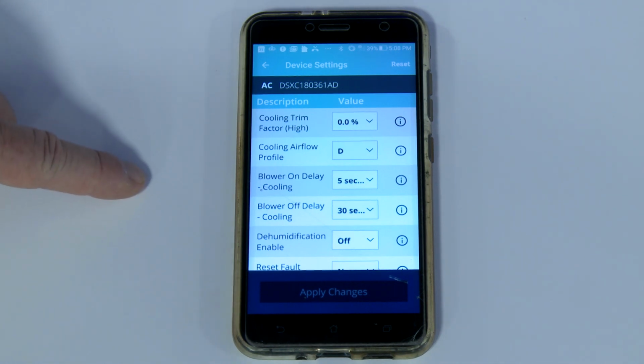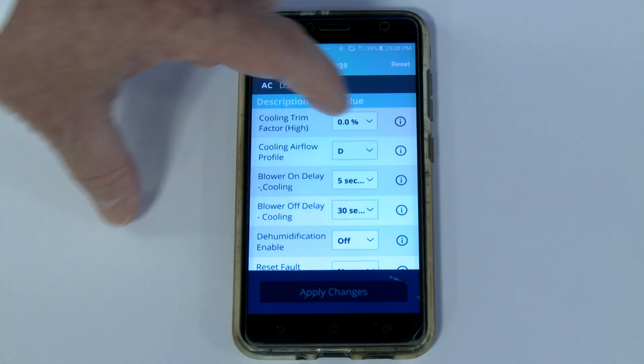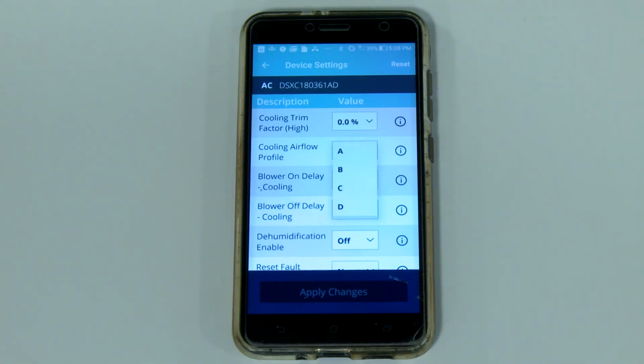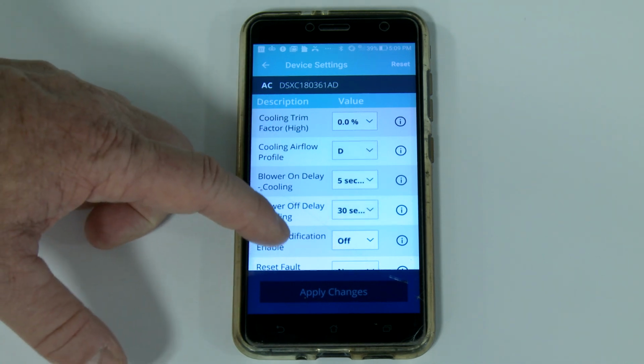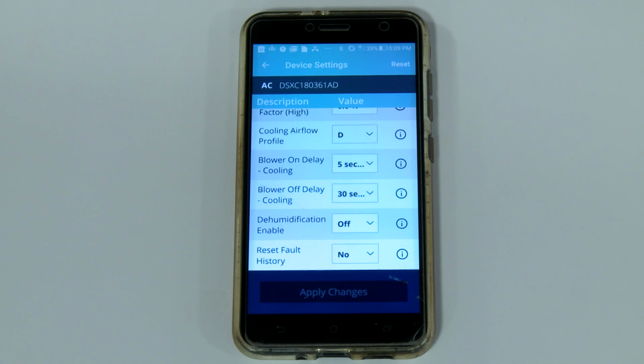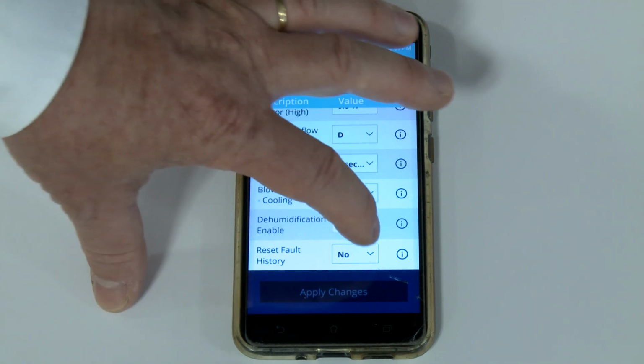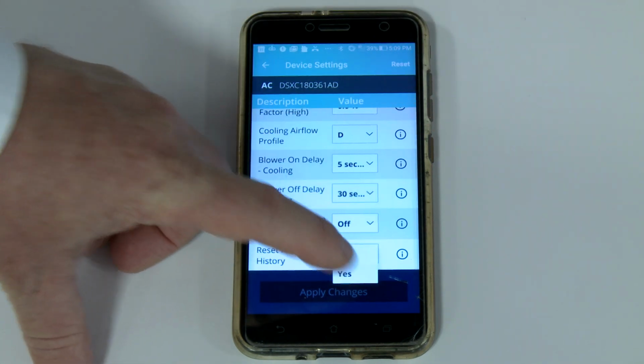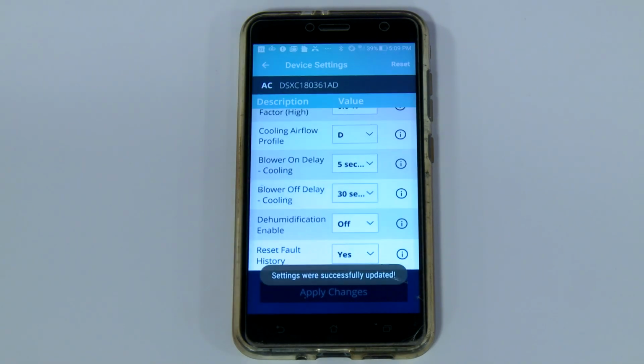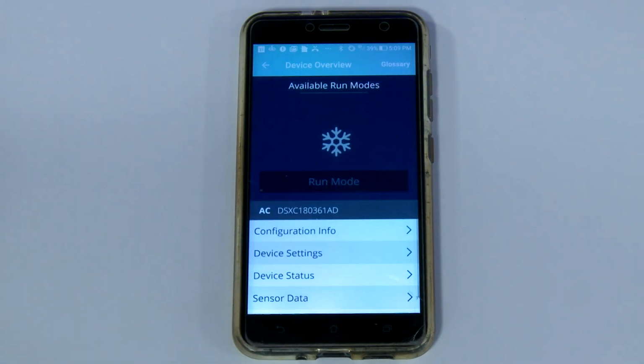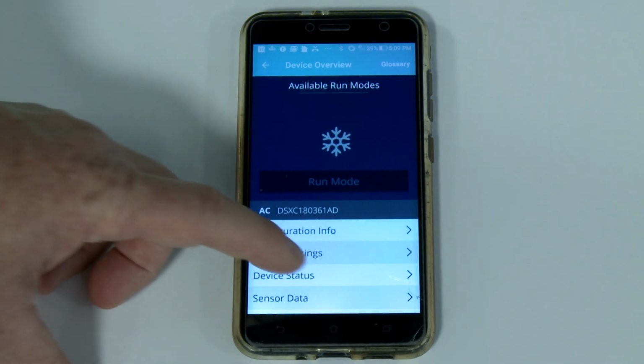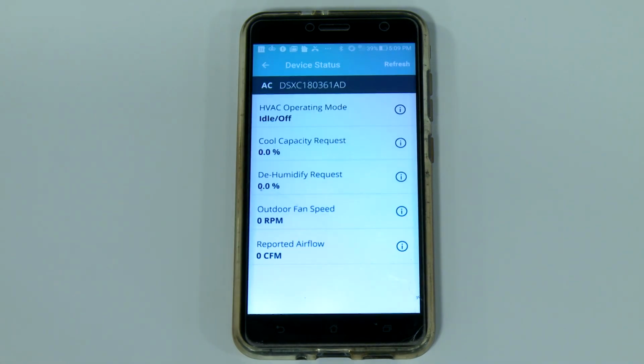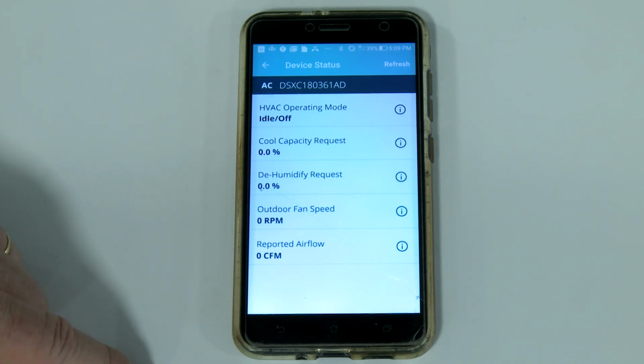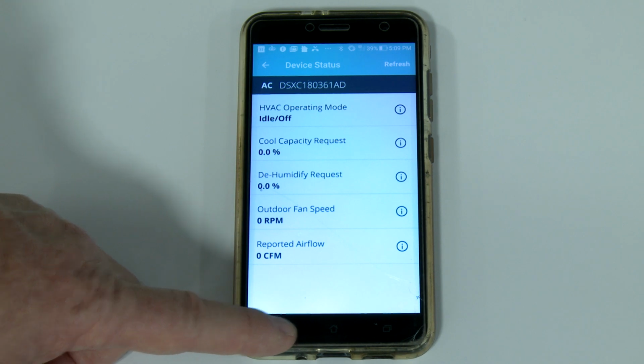Currently, the cooling airflow profile is set to D. That is by default, but you can set that to any of the 4 settings that are listed on the screen. Scroll down and you'll find many other menus, one which gives you the ability to reset the fault history. Simply select Yes, hit Apply Changes, and the changes are applied. The ability to check the device status to view the operational characteristics of the outdoor unit is possible too. In this example, the unit is idle and has no operational characteristics to report at this time.